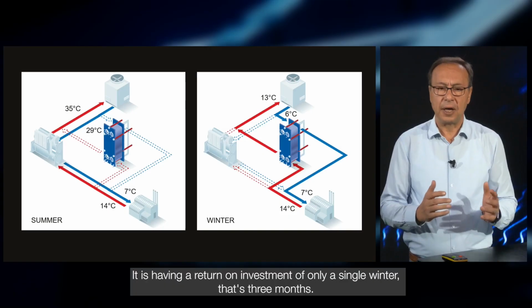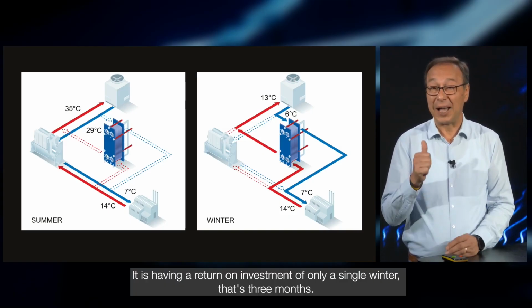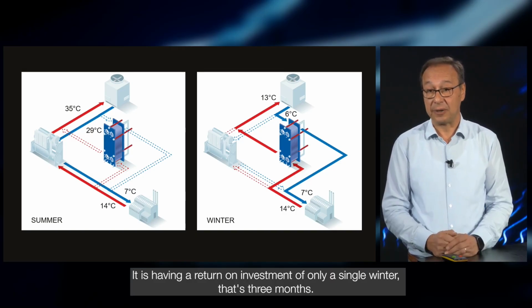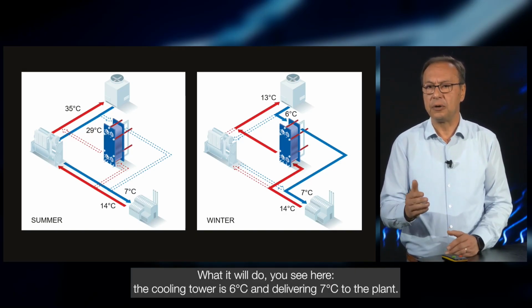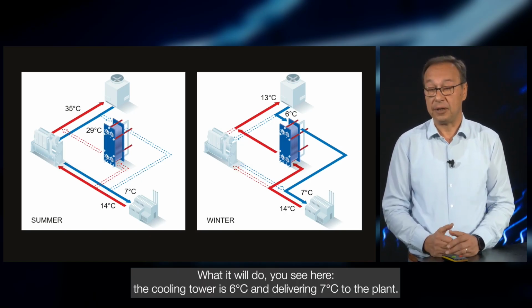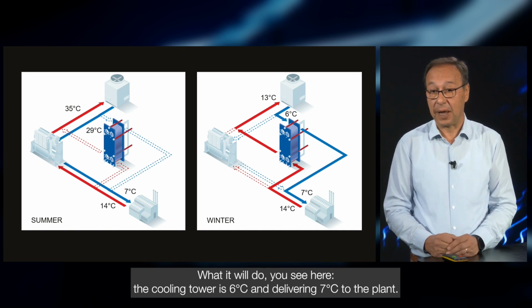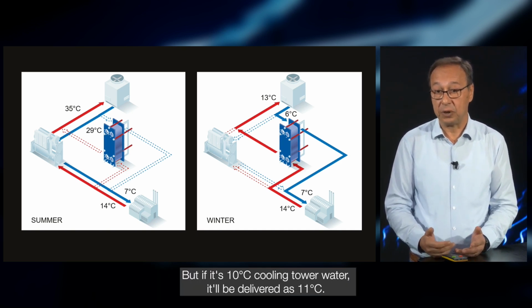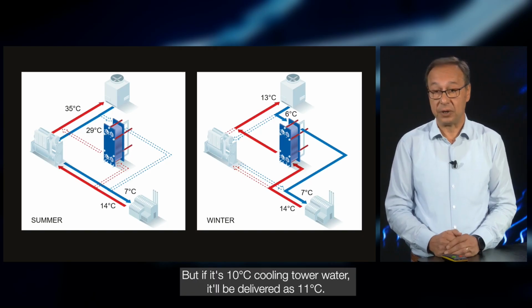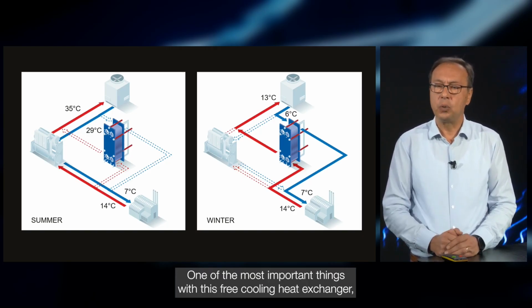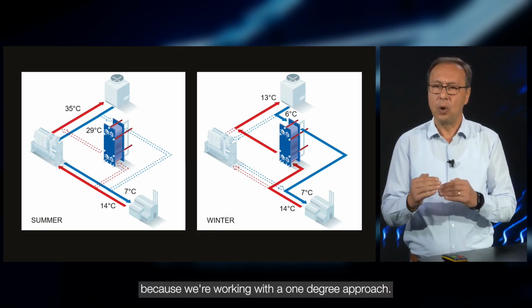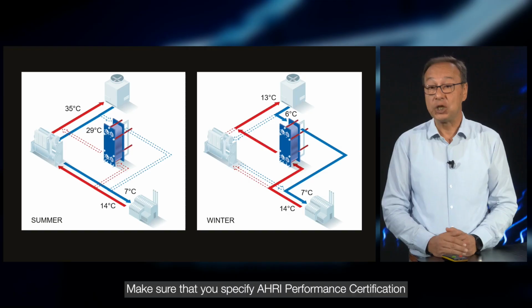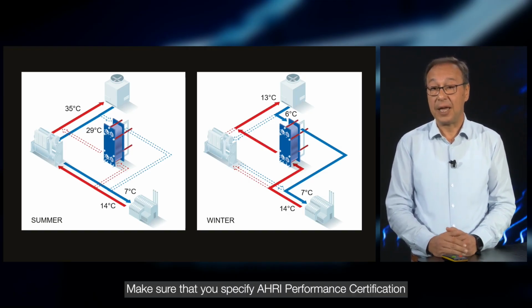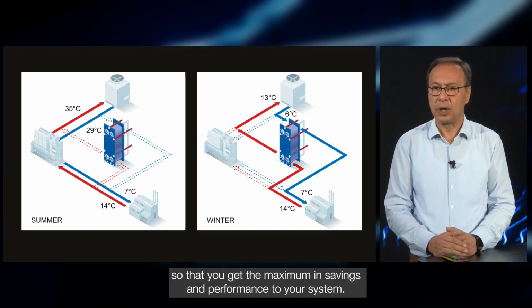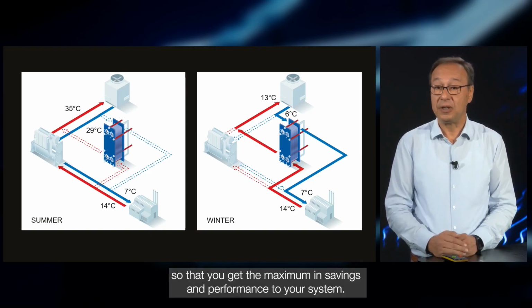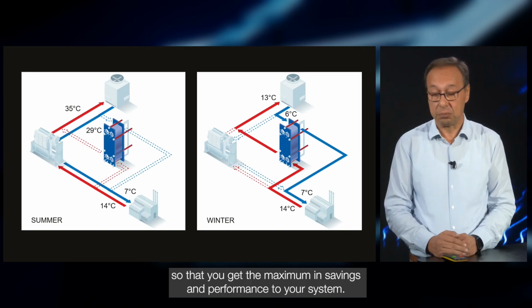It has a return on investment of only a single winter, that's 3 months. Here the cooling tower water is at 6 degrees and delivers 7 degrees Celsius to the plant. If it's 10 degrees Celsius cooling tower water, it'll be delivered as 11 degrees. One of the most important things with this free cooling heat exchanger, because we're working with a 1 degree approach, is to make sure that you specify AHRI performance certification so that you get the maximum savings and performance for your system.